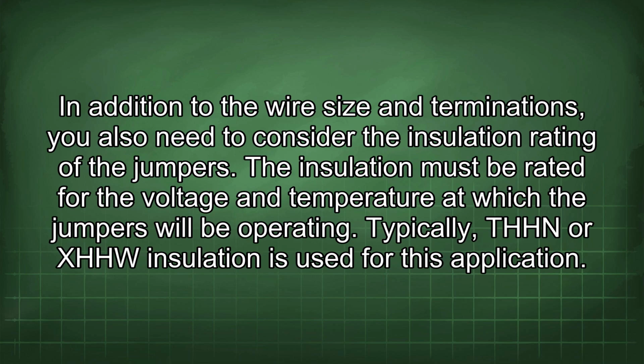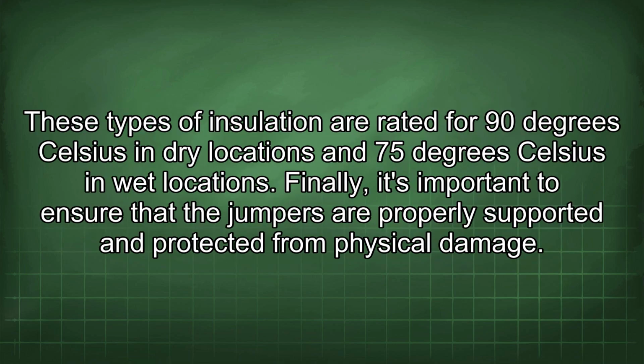In addition to the wire size and terminations, you also need to consider the insulation rating of the jumpers. The insulation must be rated for the voltage and temperature at which the jumpers will be operating. Typically, THHN or XHHW insulation is used for this application. These types of insulation are rated for 90 degrees Celsius in dry locations and 75 degrees Celsius in wet locations.